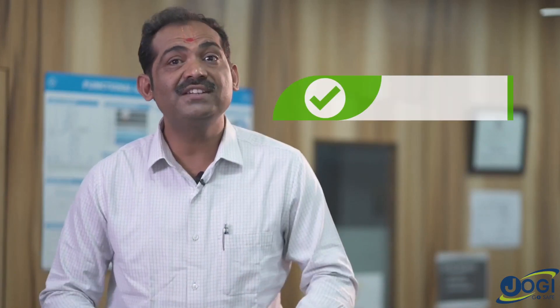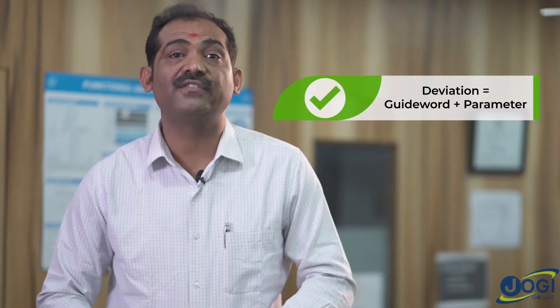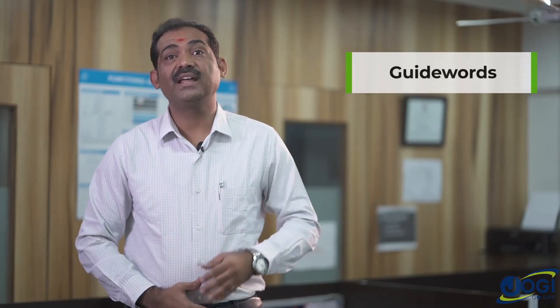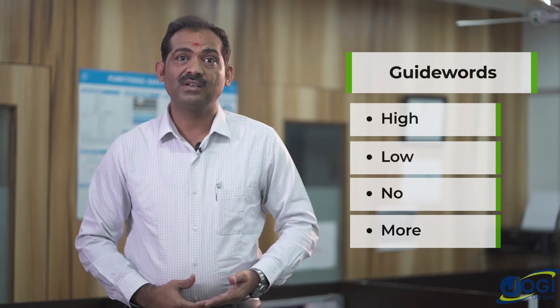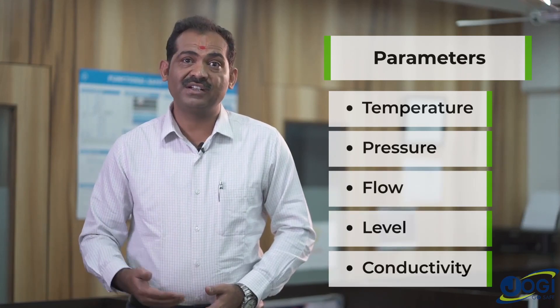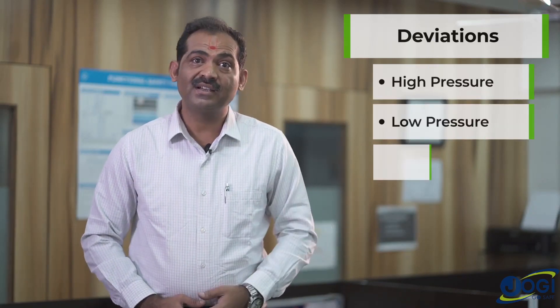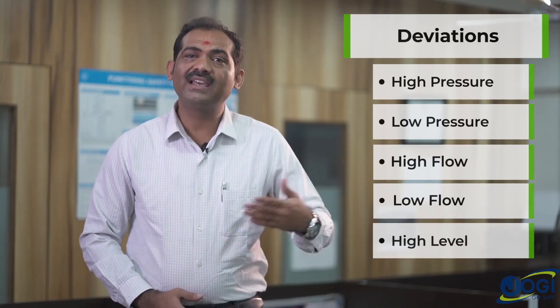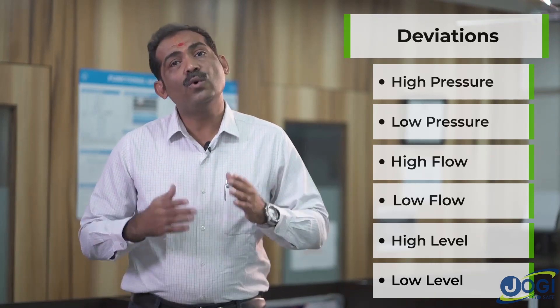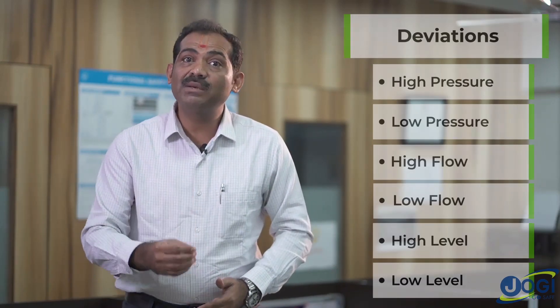HAZOP is conducted node by node. For each node we identify all applicable process deviations. A deviation is the combination of a guide word and a process parameter. Guide words include high, low, no, more, etc., and process parameters include temperature, pressure, flow, level, conductivity, pH, and so on. By combining these, we identify deviations such as high pressure, low pressure, high flow, low flow, high level, low level, and so forth.